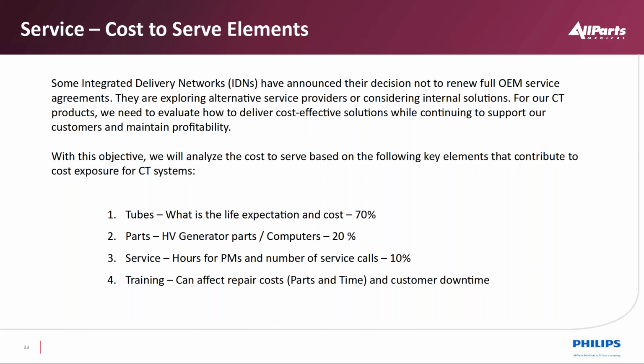But from a cost perspective, whenever you're looking at servicing a scanner, with tubes, when I do a program for a tube, I'm looking at cost to serve, a benefit analysis of what to do direct service on. The weighting factor is, do I have an X-ray tube available? And what's it cost to do a service delivery plan or a business plan? Also, are the parts available to support that X-ray tube? High voltage generator parts, tanks, and then computers, and then how many hours are dedicated to PMs and service calls, and then training. Training is one aspect a lot of people have a misconception about.